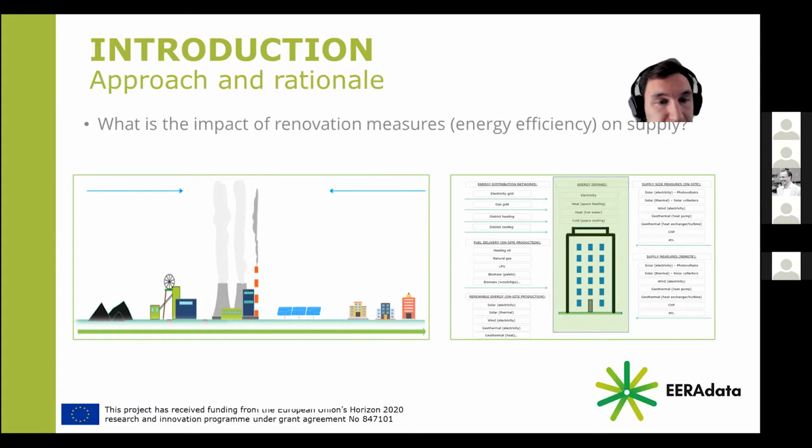Within the EU context, the concept is known as primary energy factors, which were introduced, for example, with the Energy Services Directive in 2006. But very generally speaking, a primary energy factor of 2.5 implies a 40% generation efficiency and 60% are losses. So if we wish to make an analogy to thermodynamics for those engineers out there, very roughly speaking, 40% would be exergy, before taking into account the efficiency of the devices using the energy, and 60% would be entropy, or the energy that we basically throw away. And that is a very rough concept of what we want to do.